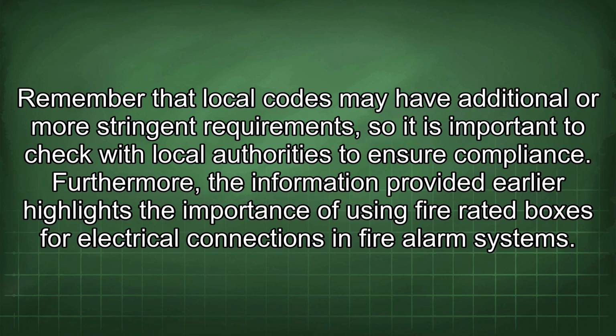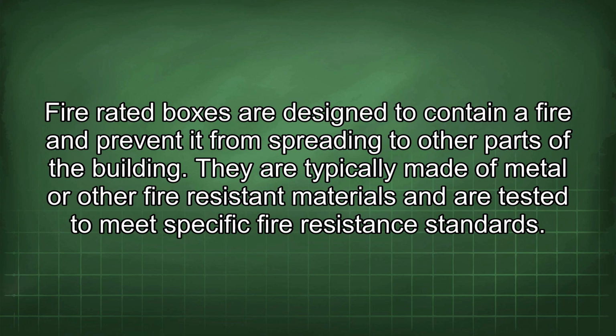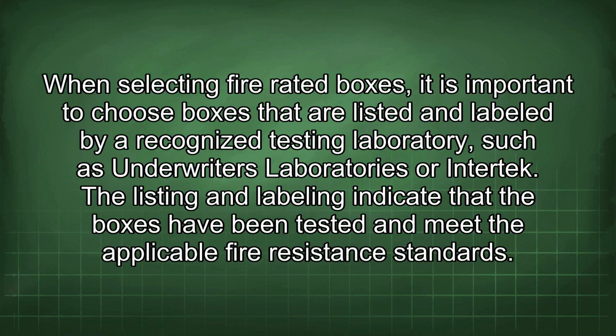fire alarm systems. Fire-rated boxes are designed to contain a fire and prevent it from spreading to other parts of the building. They are typically made of metal or other fire-resistant materials and are tested to meet specific fire resistance standards. When selecting fire-rated boxes, it is important to choose boxes that are listed and labeled by a recognized testing laboratory, such as Underwriters Laboratories or Intertek. The listing and labeling indicate that the boxes have been tested and meet the applicable fire resistance standards.